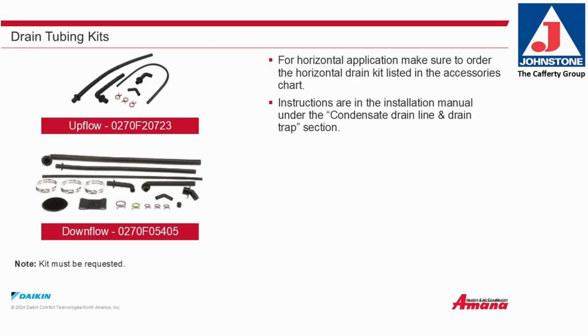Drain tubing kits. For horizontal application, make sure to order the horizontal drain kit listed in the accessories chart. Instructions are in the installation manual under Condensate Drain Line and Drain Trap section. The part numbers for the upflow and downflow drain kits are shown on the left. Please note, the drain kits must be requested when ordering the furnace.